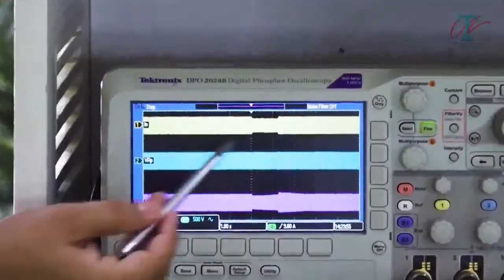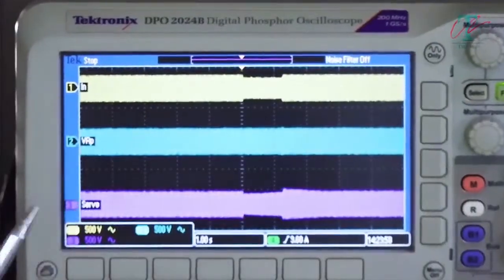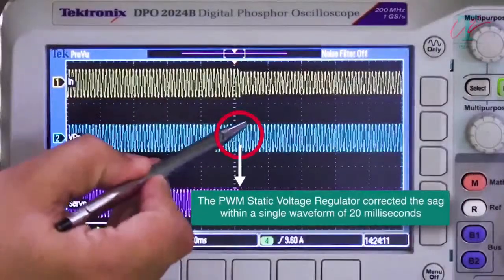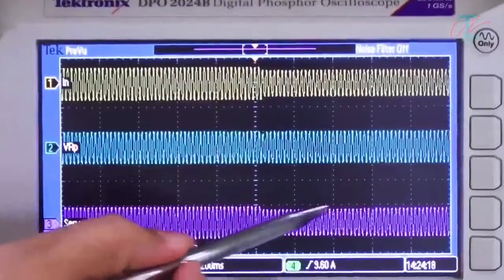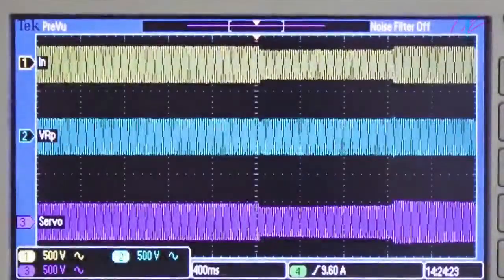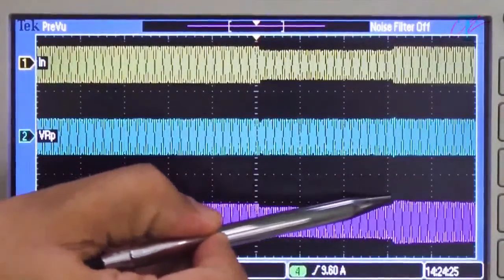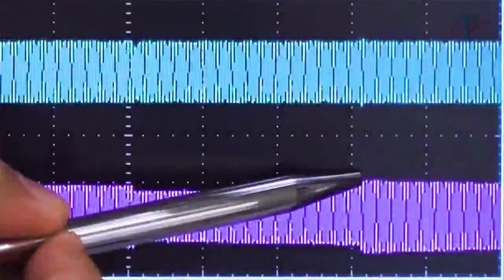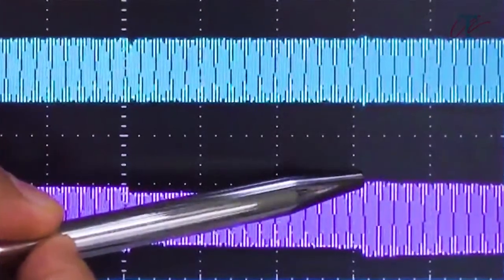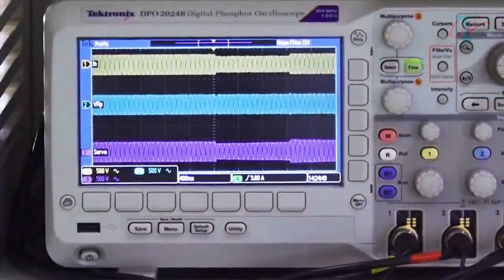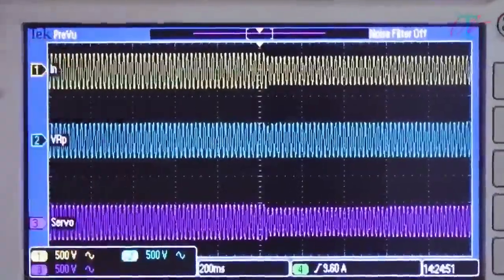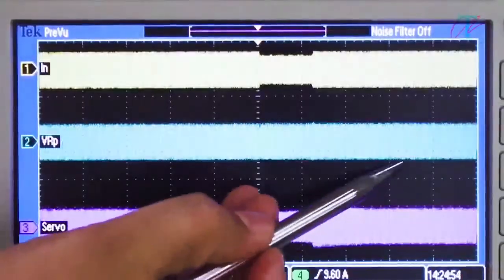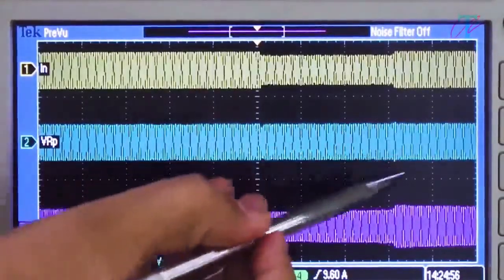As you can clearly see, a sag occurred on the input side of both the equipment, and both the equipment behaved very differently. The static voltage regulator corrected the sag within a single waveform of 20 milliseconds, but the servo voltage stabilizer took a very long time to correct. Furthermore, in the case of servo voltage stabilizer, as soon as the sag disappeared, servo stabilizer gave a high voltage output because it was still in its boost mode. If this output high voltage was beyond the cutoff limit, then servo voltage stabilizer would trip. But nothing of this sort happened in the case of static voltage regulator. You will observe from its waveform that it corrected everything within one waveform or within 20 milliseconds.